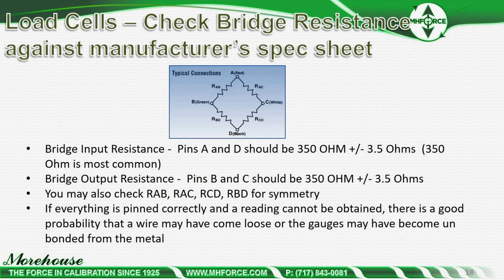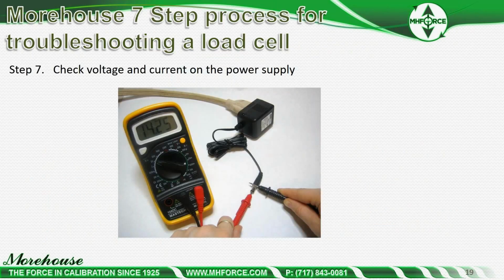If you see 349 and you see 370 for the ohms, chances are it's overloaded. If you don't see anything when you pin A and D, the gauge, as this load cell is overloaded, and the gauge has more than likely come off the metal. So if everything is pinned correctly and a reading cannot be obtained, like I said, it's become unbonded from the metal. And then step 7, check voltage and current on the power supply.